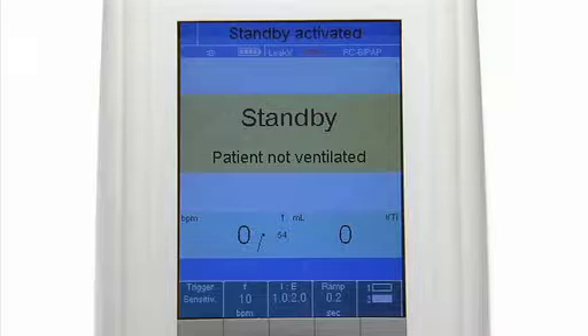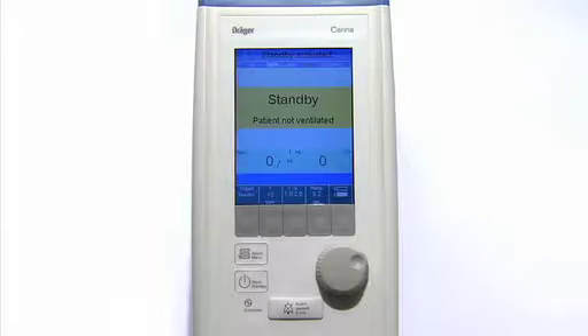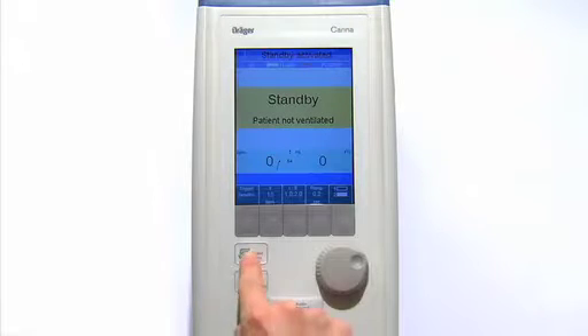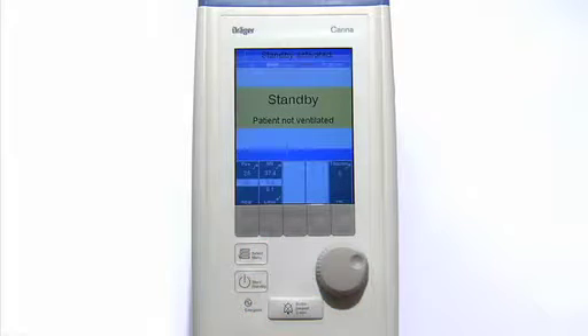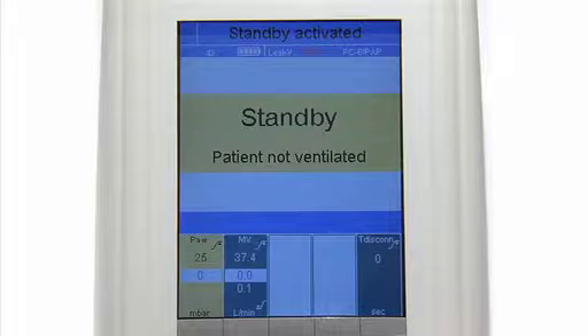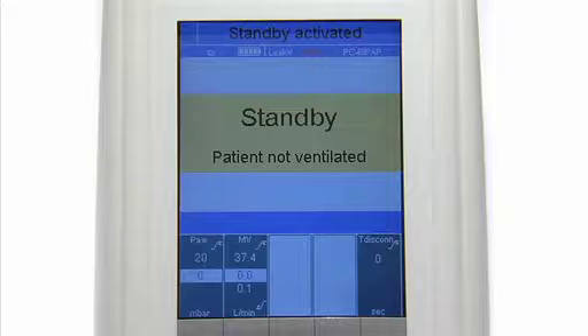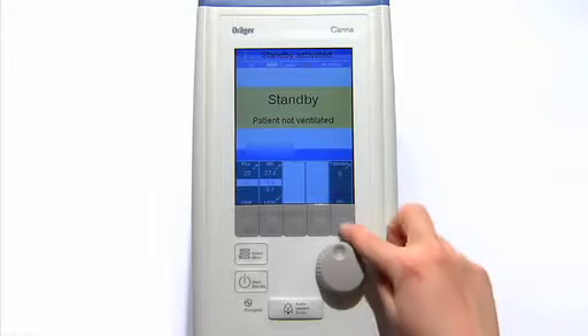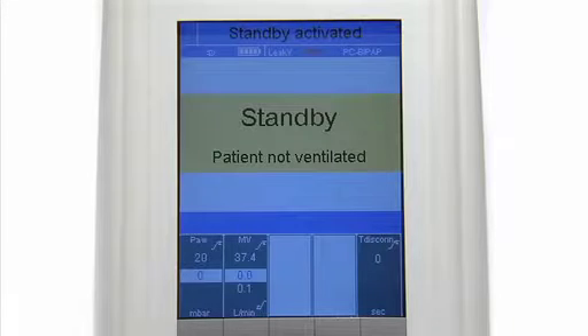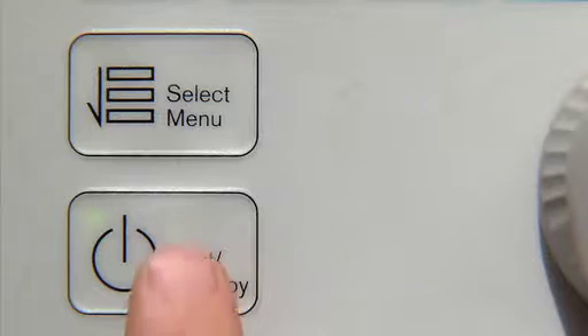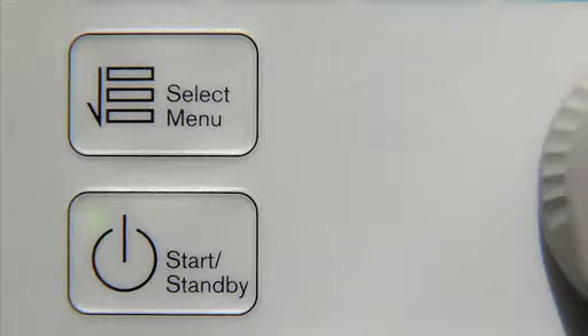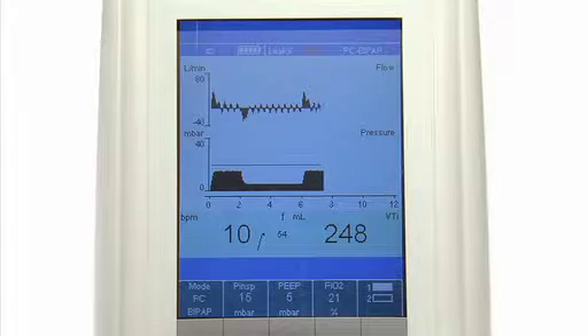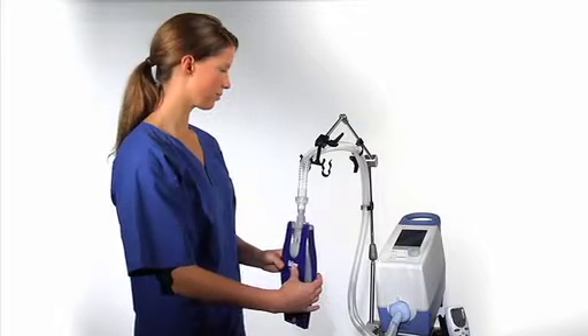Ramp 0.2 seconds. To set the alarm limits, please press the button Select Menu, then press the button Alarms and set the alarm limits. Airway pressure high to 20 millibars. T disconnect 0 seconds. Please press the Start Standby button. Ventilation will now begin. Please compress the test lung.